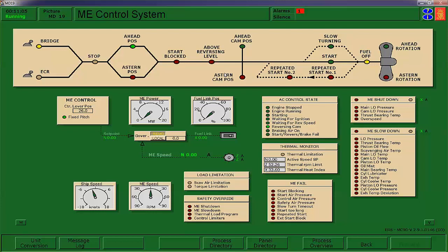Then what happens is, okay, we just came off the stop. We've got a start initiated, and you can also see it here. It went from starting air to waiting for ignition, and the engine started. That's one of the things you want to be watching for. You're waiting to see, did it actually start? If it didn't, you can go into a repeat start. And if that fails to start on the third try, then you will get an alarm in the engine room. You need to be conscious of that. You need to have been watching for that eventuality, so you're already moving and working on the problem.